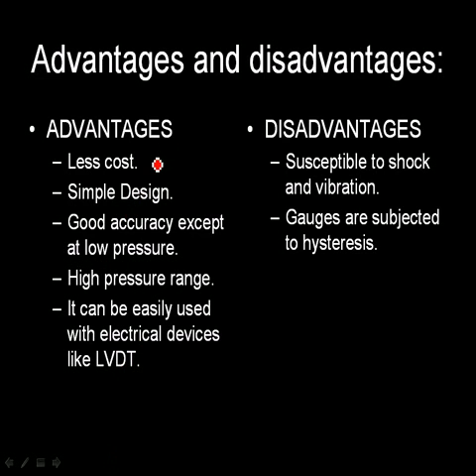It has less cost, simple design. Yes, it can be constructed quite easily. Good accuracy except at low pressures. As I mentioned, it is used for measuring high pressure. It has a very high pressure range, and yes, it can be easily coupled with electrical devices like LVDT. Now what are the disadvantages?